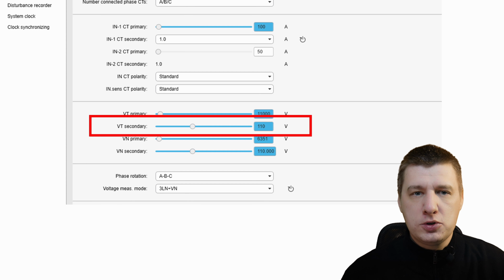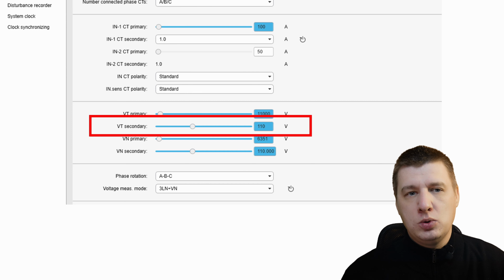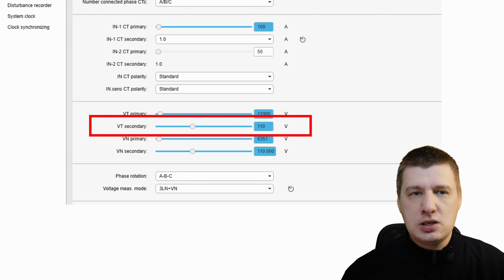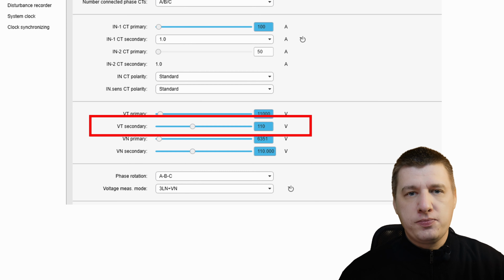Let's look at the specific example. If your network has 11,000 volts and your transformer has a ratio of 11,000 volts to 110 volts, you must set your VT secondary to 110 volts. This creates a mathematical bridge. When the relay detects exactly 110 volts at its back terminals, it uses your scaling settings to display 11,000 volts on the HMI screen. This setting is critical for your protection functions, like under voltage or over voltage. If you tell the relay the secondary is 110 volts, but actually it is 100 volts, every measurement will be off by 10%, potentially causing the relay to trip when the system is actually healthy, or worse, stay silent during real faults. The P5 is very flexible, allowing you to set the VT secondary anywhere from 75 volts to 200 volts.